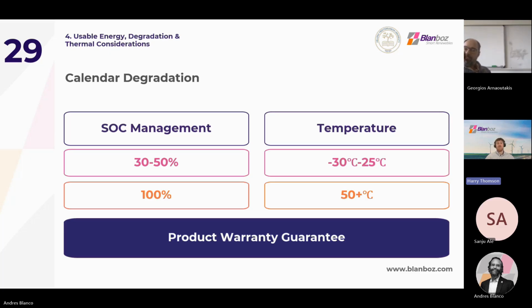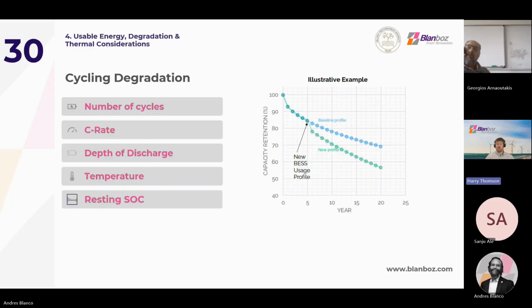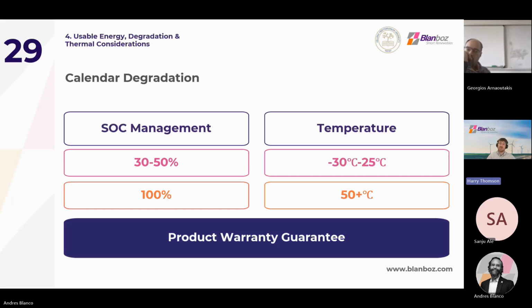On the other hand, we have temperature. In our experience, the recommended storage temperature for LFP has been about -30 to 25 degrees Celsius to minimize the rate of degradation. This can increase dramatically with temperature. So if the temperature is stored at, say, 55 degrees Celsius, this can see up to an additional degradation of 0.6% per month on top of the existing degradation. So it's quite a lot in the grand scheme of things, especially over a long time. And it's important that these factors are all captured in the product warranty guarantee, and that where possible, the risk of delays can be identified and mitigated.